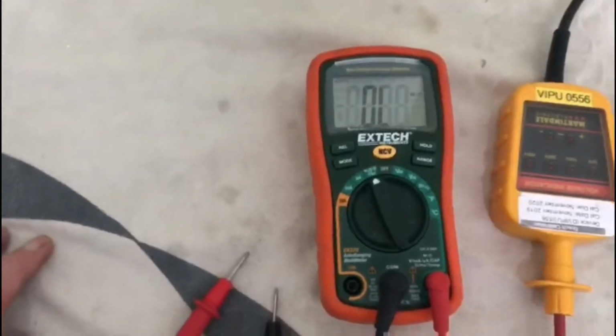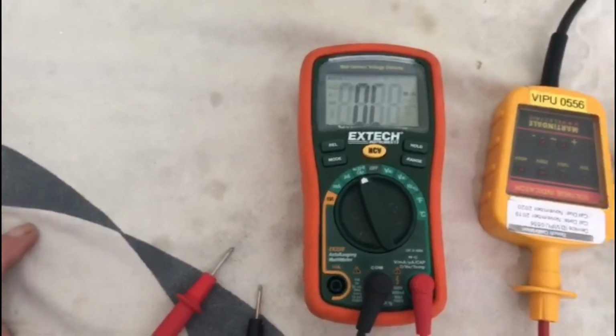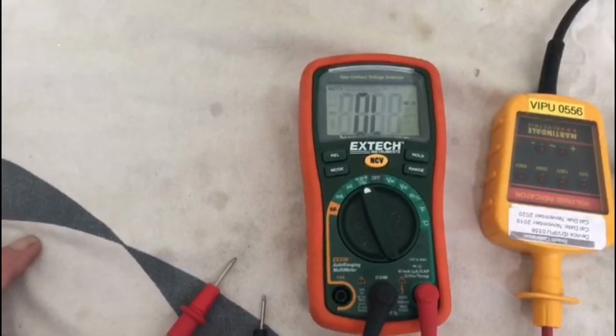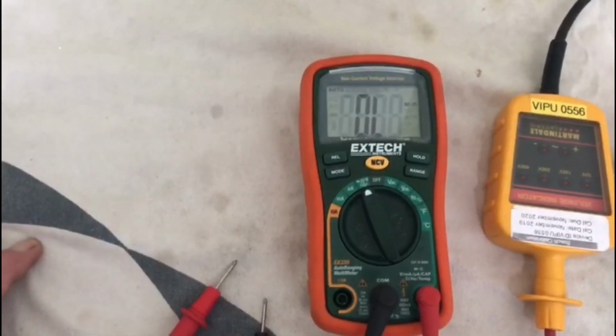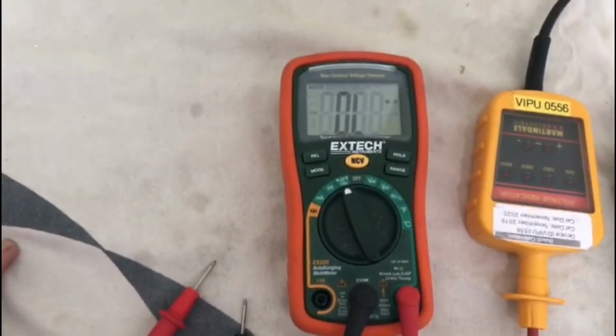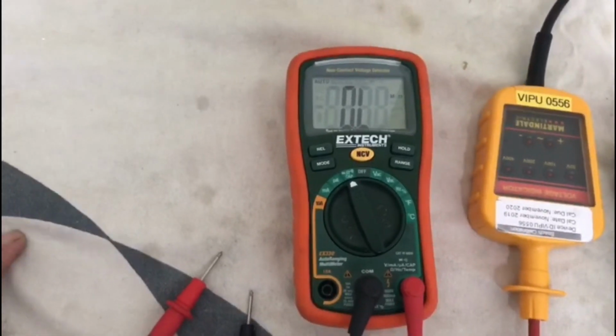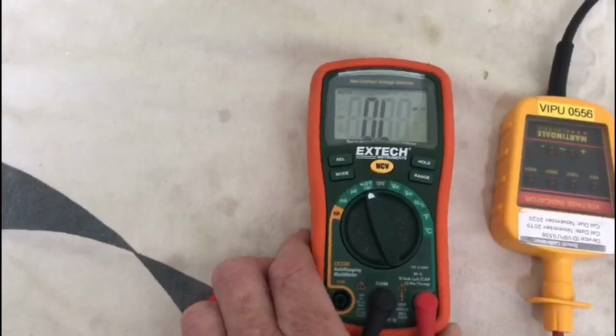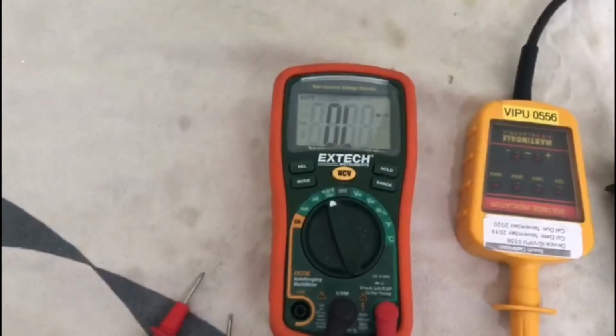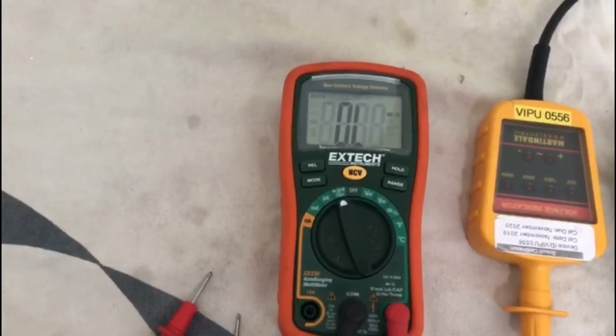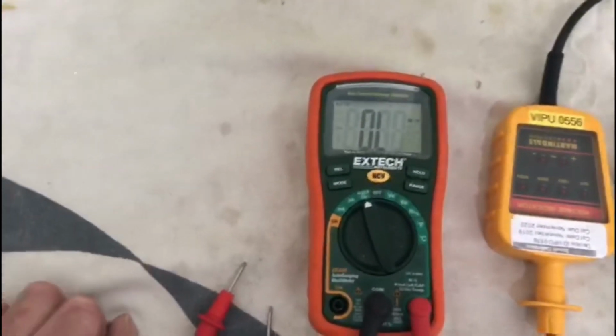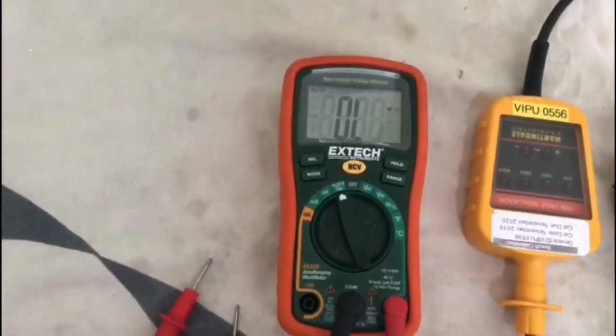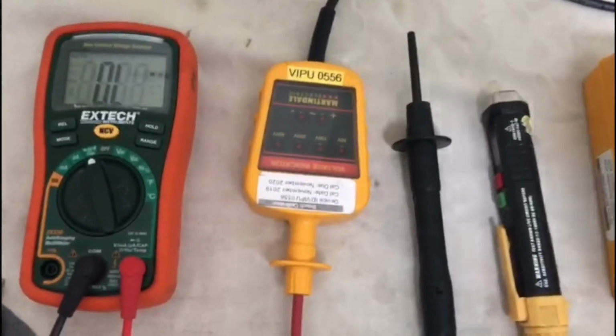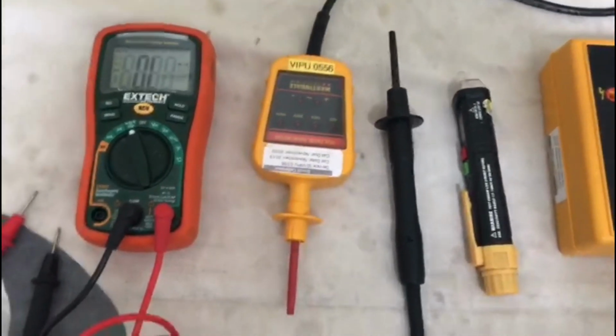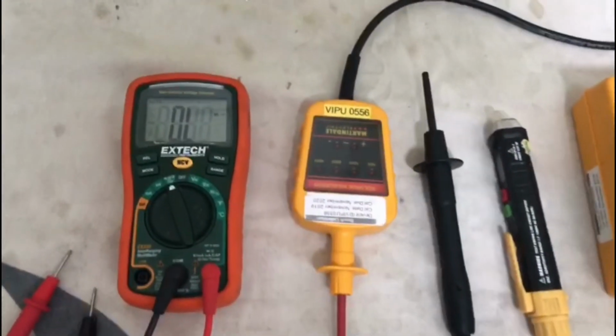So obviously if you're doing continuity testing, and say for the sake of argument your reading is 2.2 ohms, if you're getting 2.2 ohms on your multimeter, that's your base reading. In other words, you are getting continuity, but there are different readings which you get, which I will go into more depth with.